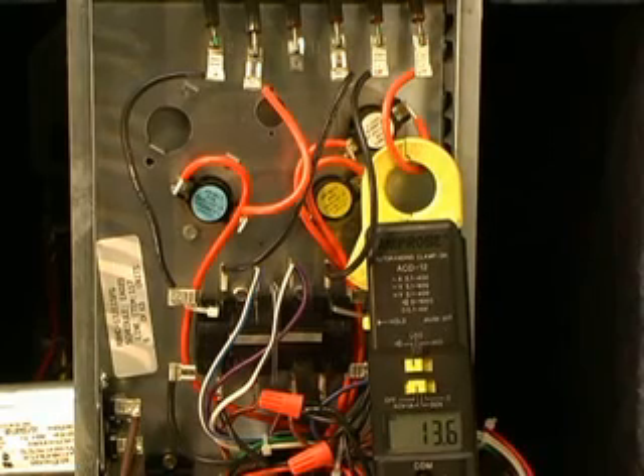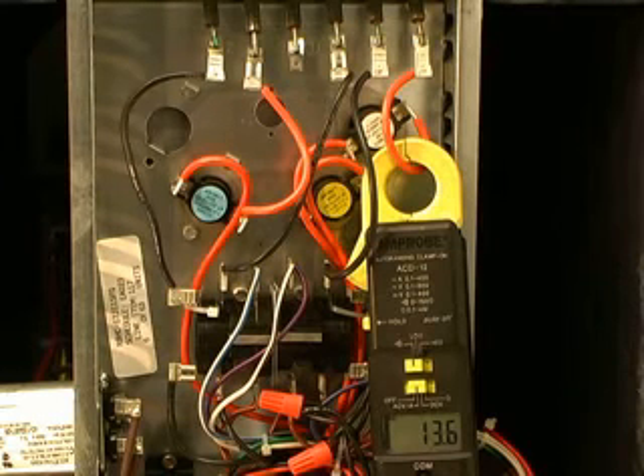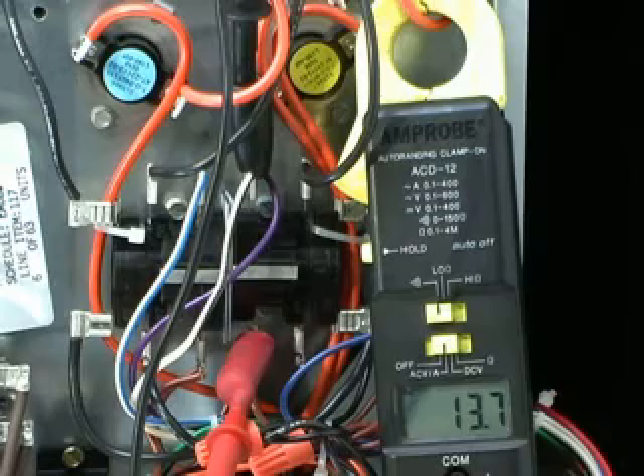So I hooked it around the first one on the right, and you can see it's pulling 13 amps. So there's the problem. All you've got to do at that point is trace the wires back down to the sequencers and see which one it's hooked to, and you know which sequencer is either being told to be on or it's just stuck on. So at this point, you'd have to go to the 24 volt connection and make sure that something wasn't telling it to come on.